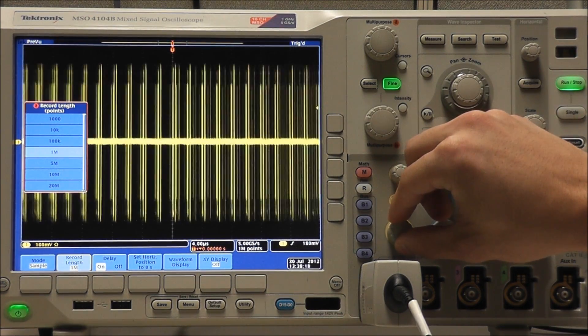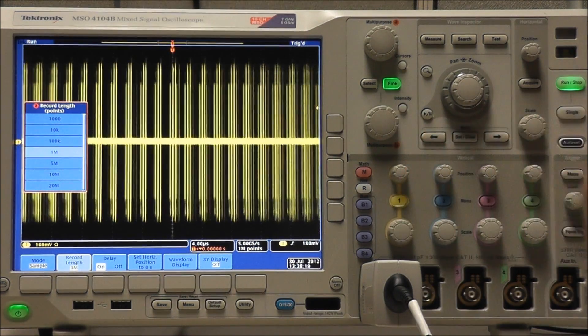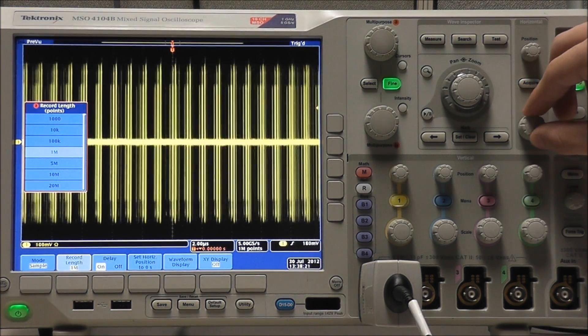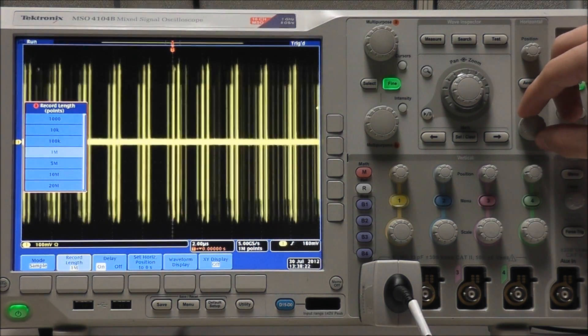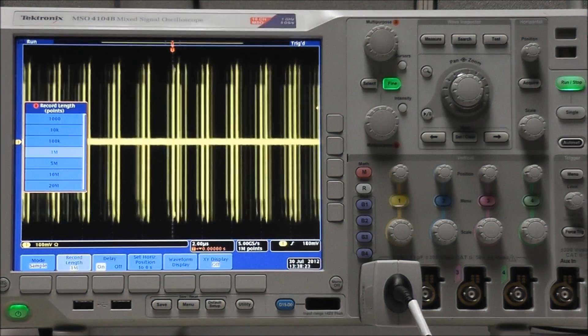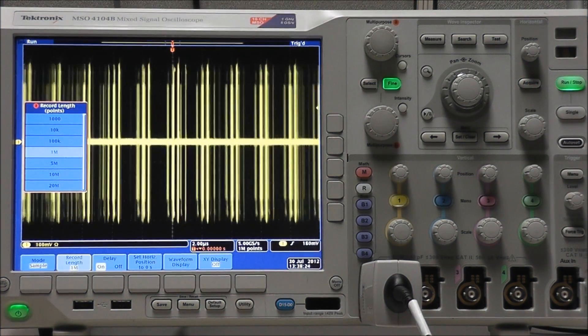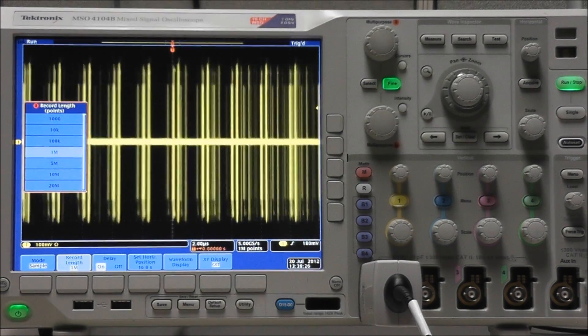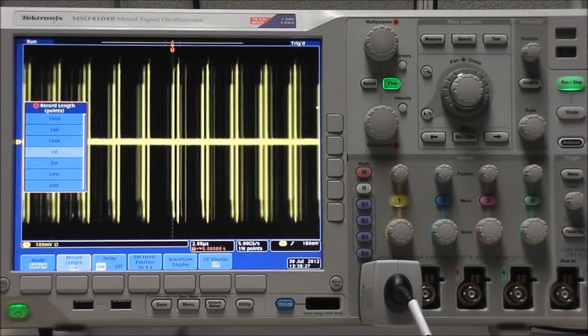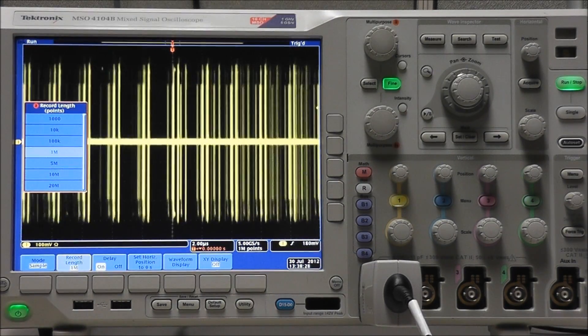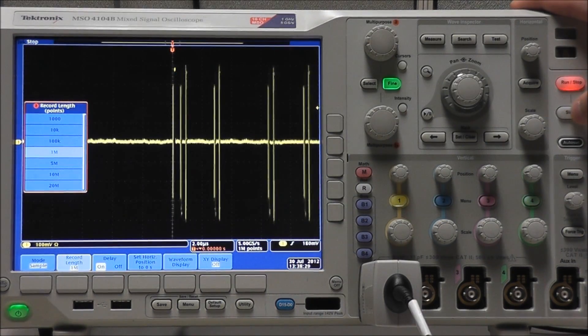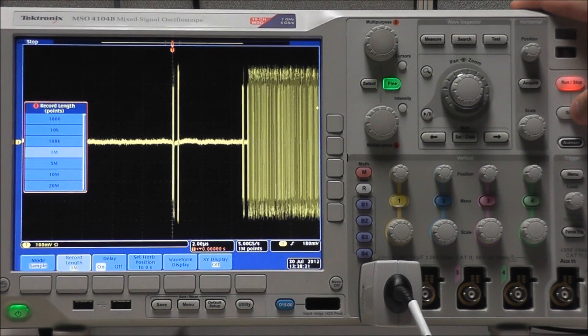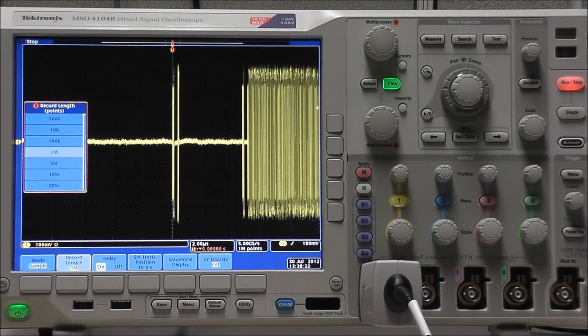We can adjust the vertical and horizontal scaling as necessary. Select Single Acquisition until we get a nice example of a data packet.